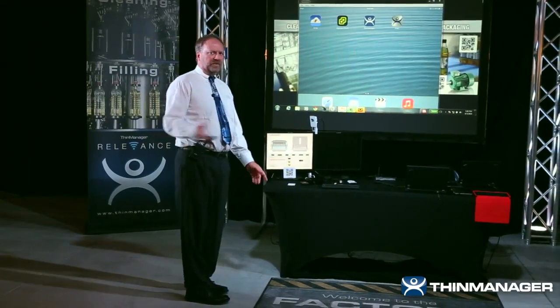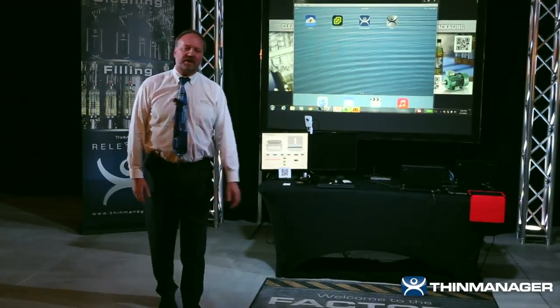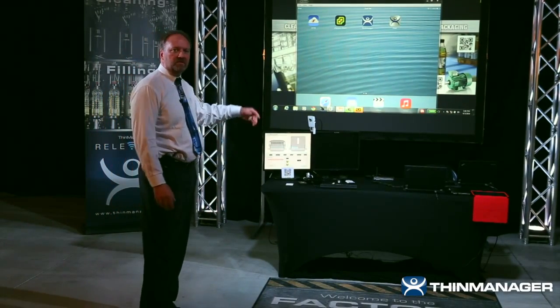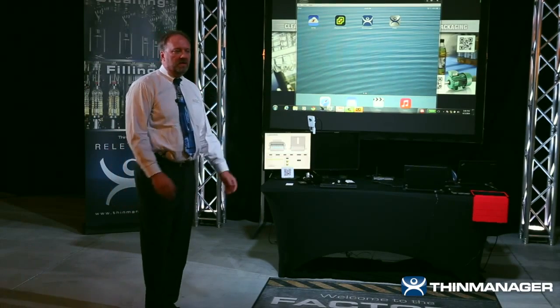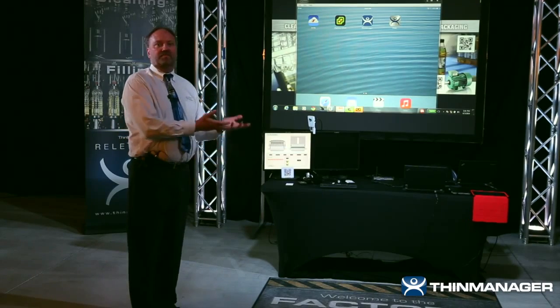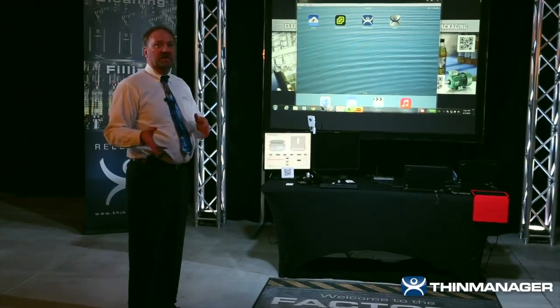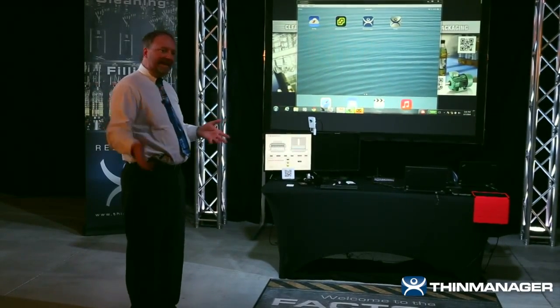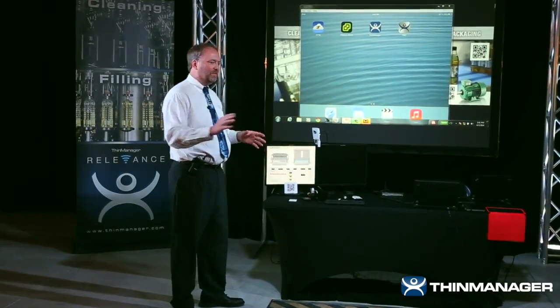Oliver, who can't really fix this, calls Manny and says, 'Hey Manny, I've got a problem — some of the bottles aren't coming out clean.' Manny knows it's probably one of the valves, but the problem is there are maybe 24 or 48 valves in this linear process. While the process is running, you really can't tell which one's not working properly — you have to do a process called manual control and visual inspect.